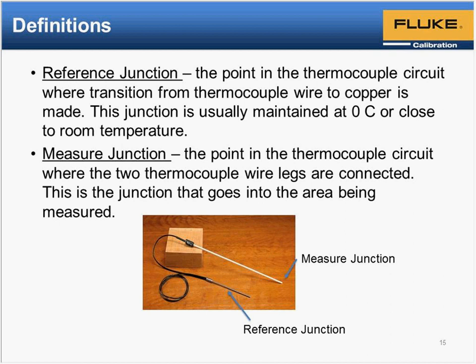A lot of labs use a water torch. They're really handy because you don't have acetylene or hydrogen. You just use water and a chemical that produces hydrogen. I don't know exactly how it works, but it makes a very, very small flame, like the tip of a pencil, and you can use that to heat up just the very tip of the wire and then weld the wires together. Laboratories also use spot welders that some manufacturers make, where you just take two wires and push them inside the welder, push a button, and it arcs the wires together in a nice, simple way. Sometimes they're just not quite as clean as somebody doing it with a pencil torch. But anyway, just some different thoughts there on making the measuring junctions.